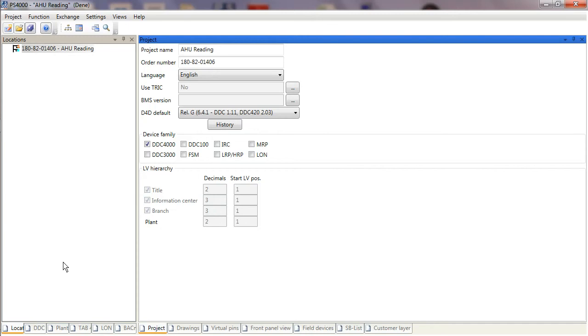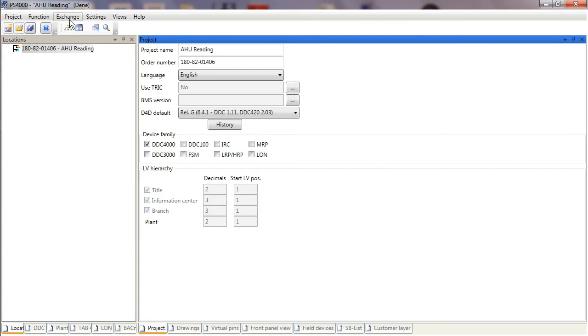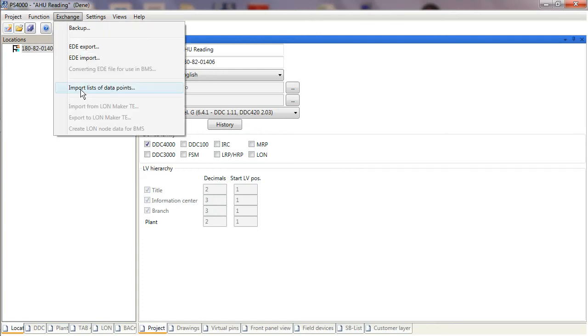What I want to do is avoid all of that trouble by using something called data point import. Because I've got data points already allocated to a specific location, if I bring the data points in, it will create the location tree for me. All I then have to do is rename them to be the locations that I want. It's a bit like reverse engineering but it saves a hell of a lot of work. Let me demonstrate this by carrying out the process.